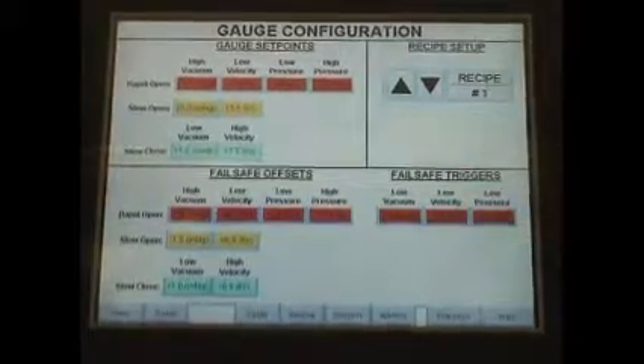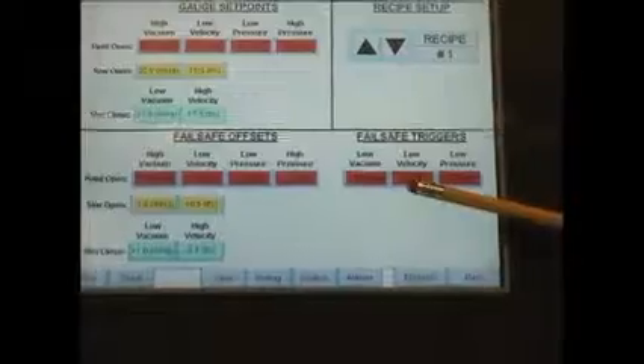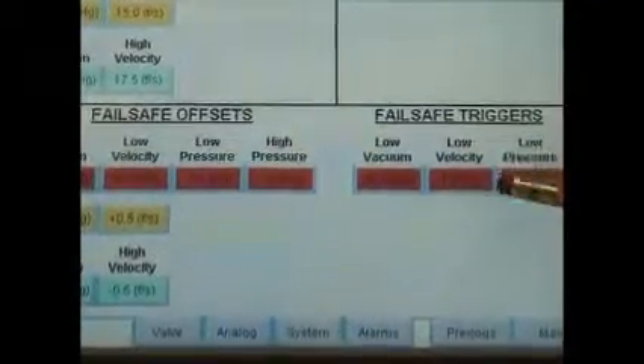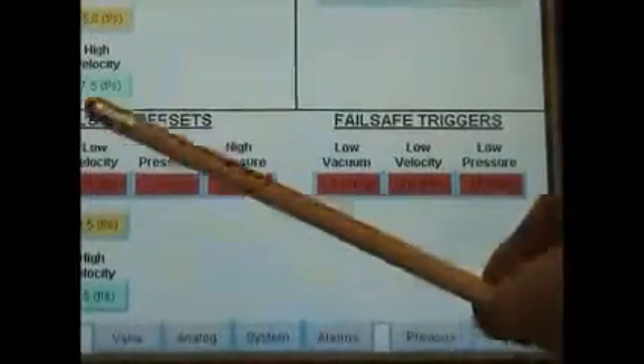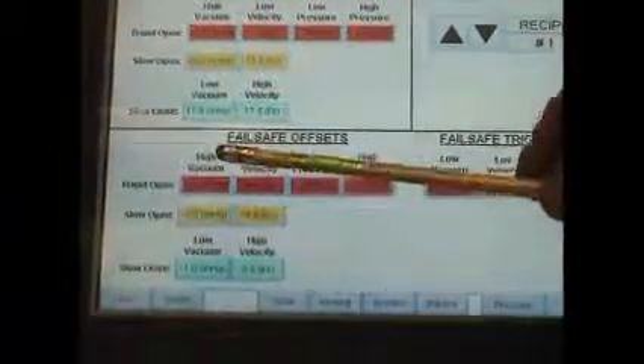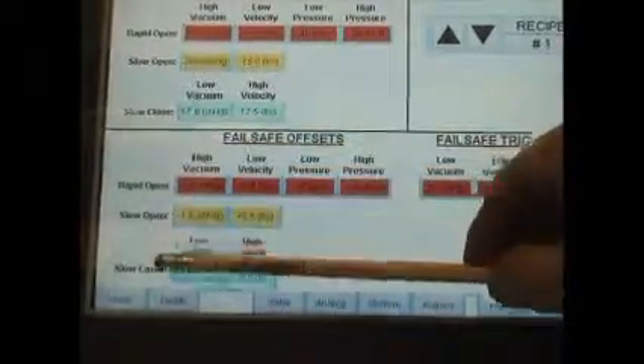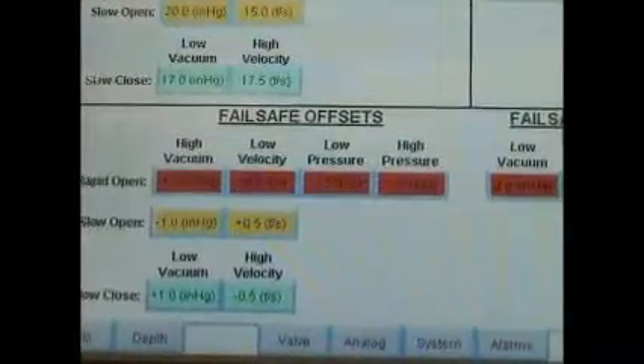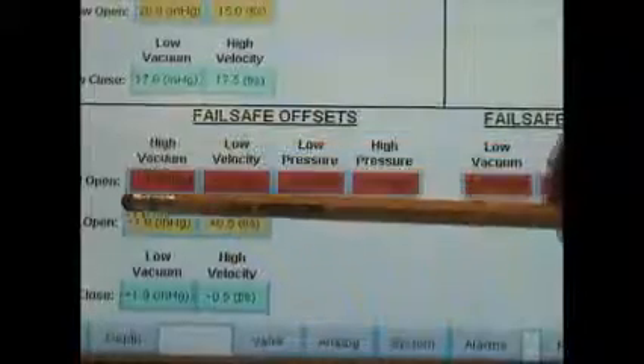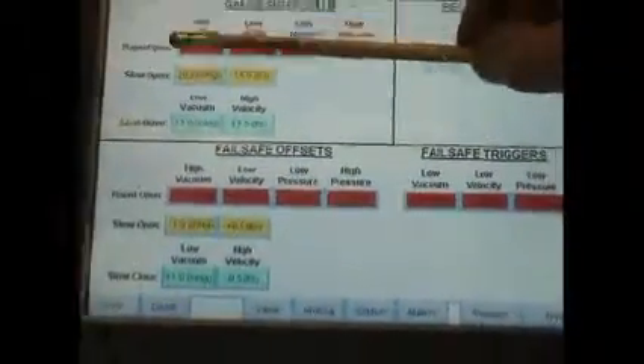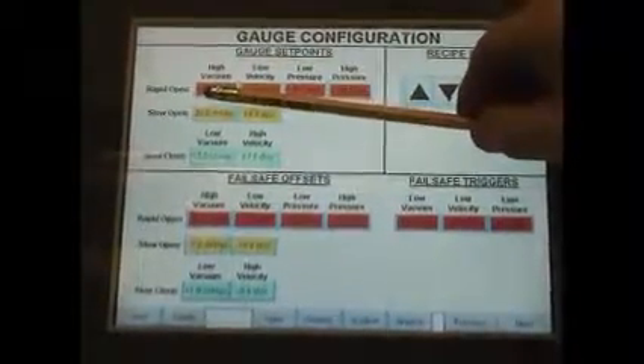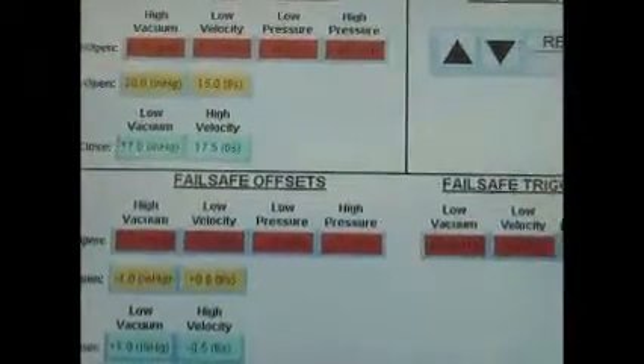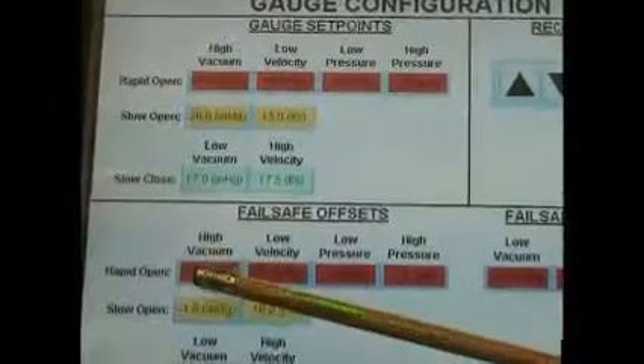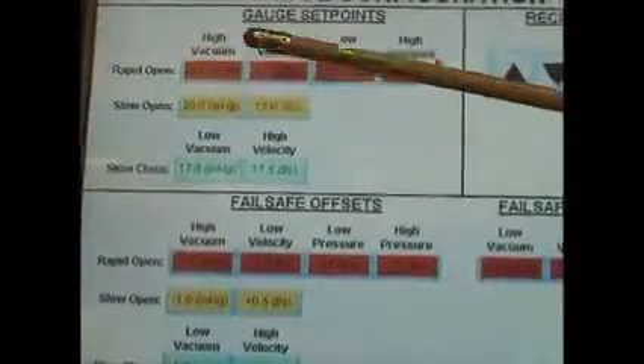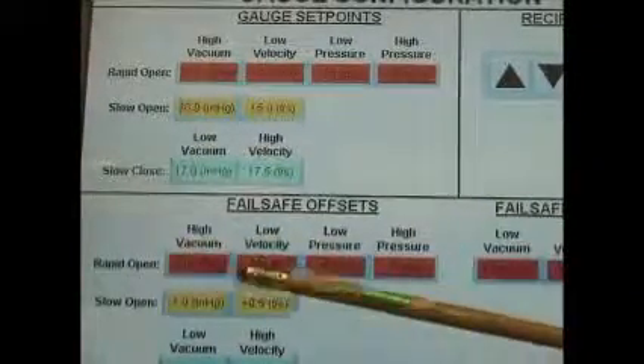With the case of the velocity meter, we've got our fail-safe trigger set at 3 feet per second. This also could be in meters per second. Assuming that the velocity meter no longer works or a velocity drops below 3 feet per second, our fail-safe offsets are going to come into play. As we can see here on our vacuum, for example, assuming our velocity meter has failed, our fail-safe offset on the vacuum is going to be reduced by 1. In other words, right now we have the vacuum to trigger rapidly open at 25. If the velocity meter would fail, our vacuum now is going to be less 1. In other words, it's going to rapidly open at 24 instead of 25 because we're reducing it by 1.